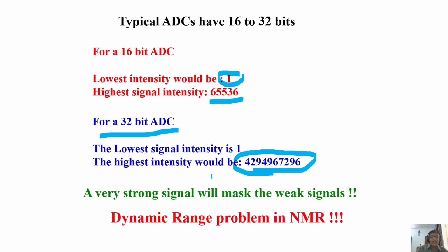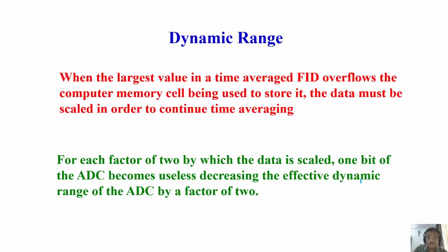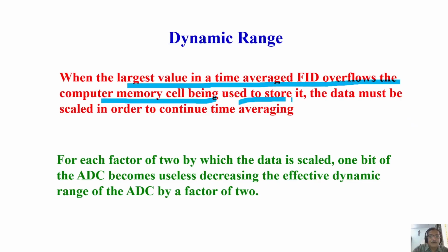And then it will overcome the problem of what is called a dynamic range. What is a dynamic range problem in NMR? I will tell you soon. What happens is, when the largest value is in the time average FID, in the sense I keep on acquiring the signal by doing signal averaging, the largest value, when it overflows the computer memory, okay, it will keep storing in the different cells of the computer. When it overflows it, the data must be scaled to continue averaging.